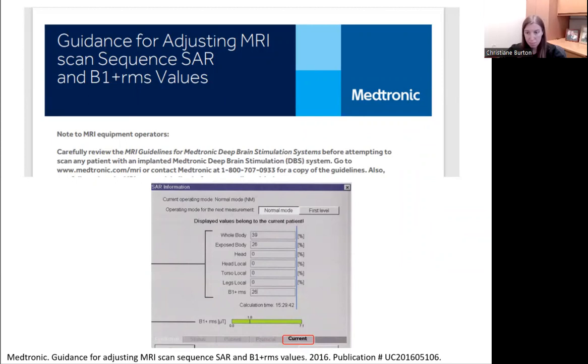This document is intended to provide general guidance on how to adjust MR scan protocols in accordance with the specific absorption rate, SAR, and B1 plus RMS limits identified in the MRI guidelines for Medtronic deep brain stimulation systems. The scan protocol adjustments described in this document should only be used by qualified MRI scanner operators. This document goes into how to configure the protocol, make adjustments to sequences, and verify the predicted B1 plus RMS value.